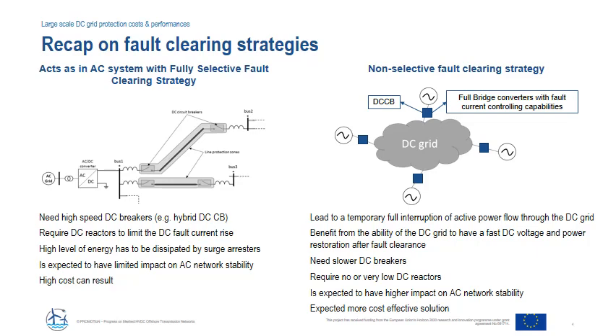Two main fault clearing concepts are generally considered for DC grid protection. The first one consists of acting in the same way as we would in an AC system with a fully selective fault clearing strategy. Each line being a protection zone, the principle lies in the rapid identification of the faulty line, followed by its isolation by DC circuit breakers installed at each line end. It generally requires fast DC circuit breakers associated with a DC reactor to limit the speed of the rising fault current. It acts fast and is expected to have a limited impact on AC network stability. However, it requires expensive, fast DC circuit breakers and, as such, can result in high costs for the protection system.